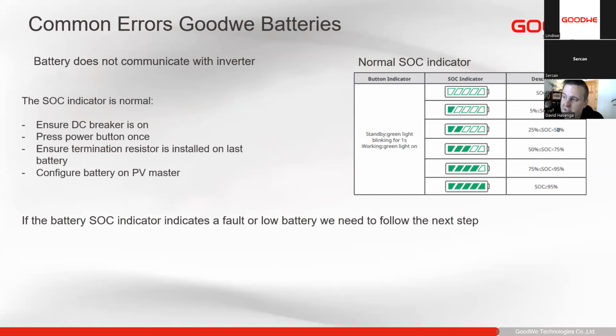If the SOC indicator is normal, we also need to make sure that our termination resistor is installed on the last battery. So if we only have one battery, it will be installed on that one battery on the open terminal. And then next, we need to make sure the batteries are properly configured on PV Master. If we have an alarm on the SOC indicator, we can view and see what the alarm is in the user manual, and that will give us an idea what we need to do. But if the indicator is showing a low battery or anything like that, we'll follow the next steps.